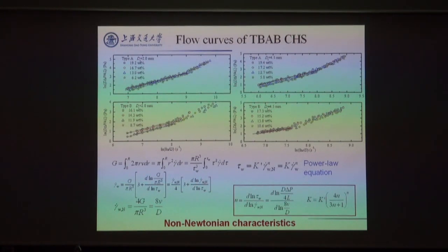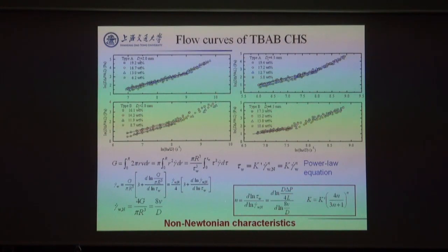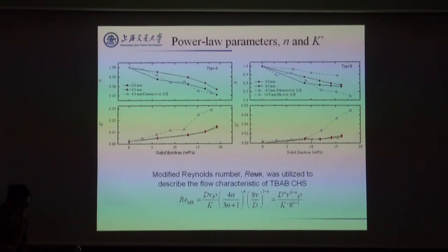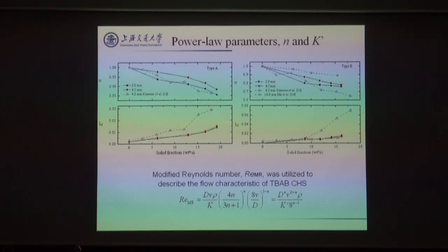Here are pressure drop results for different tubes and for type A and type B. There are clearly two branches: one for laminar flow and one for turbulent flow. Because TBAB-CHS is a non-Newtonian fluid, we applied a power-law fluid model to obtain two important parameters: the flow index n and the flow consistency parameter K'. With these two parameters we can define a modified Reynolds number to estimate friction factors. With increasing concentration, the flow index decreases and K' increases.